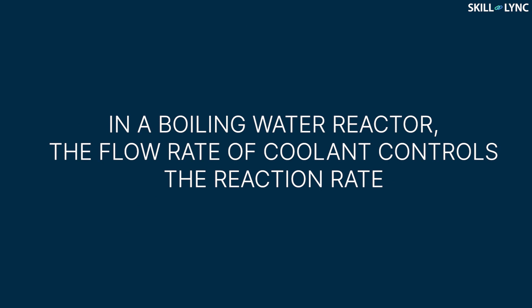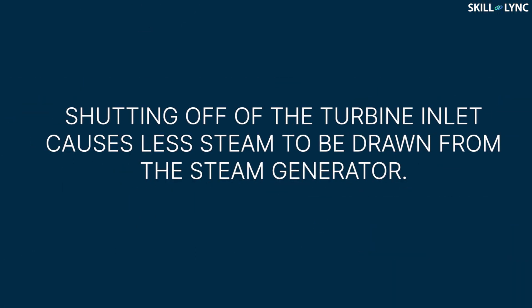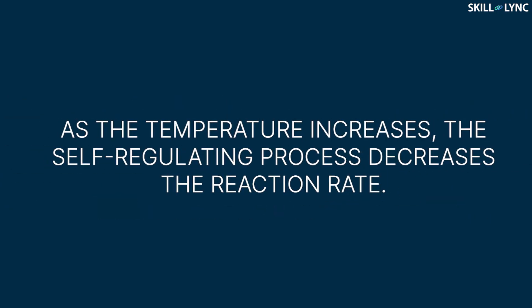Moving on to reaction control — we have seen that a boiling water reactor controls the reaction by adjusting the flow rate of the coolant. But in a pressurized water reactor, the negative temperature coefficient helps in controlling the reaction rate. To decrease power, the inlet of the turbine is shut off. This causes less steam to be drawn from the steam generator. As a result, the temperature of the primary loop increases and the power output decreases. Thus, the self-regulating process causes the temperature to return to normal.